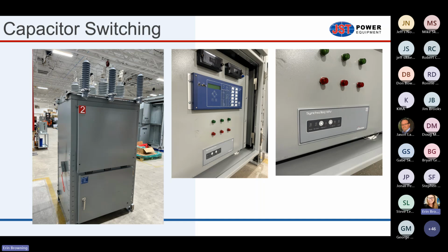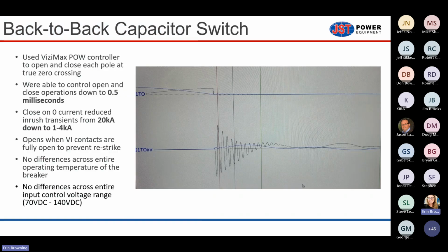Our breaker, we can control the opening and closing at zero cross on each phase because they're each individually operated. So that's what this controller is doing. It's monitoring the current voltage on each phase. It's sending a trip command to the controller. The latency that's involved with all these signals for opening and closing is accounted for in the configuration of the controller, and it gets dialed in on site and tested, and then we have zero crossing on each phase.